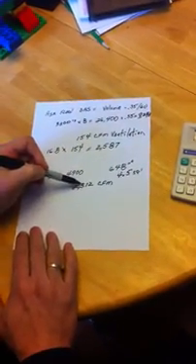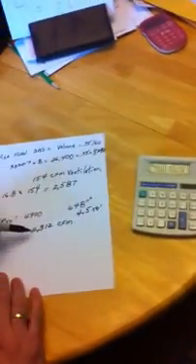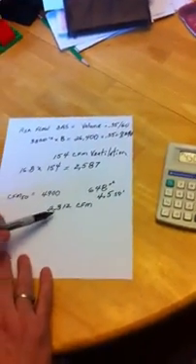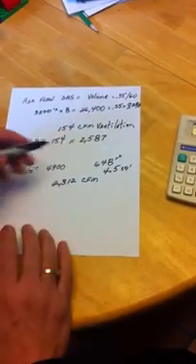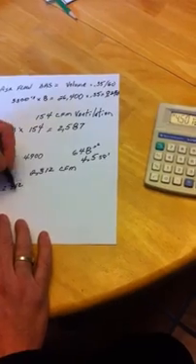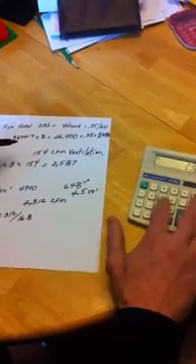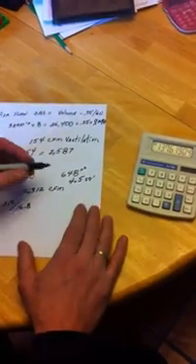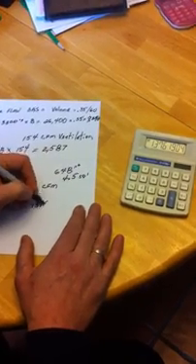Now, with 2,312 CFM, another calculation we can do is find out how much that excess air leaking out of the house is costing us. We take 2,312 and divide that by 16.8, which equals 137.6.